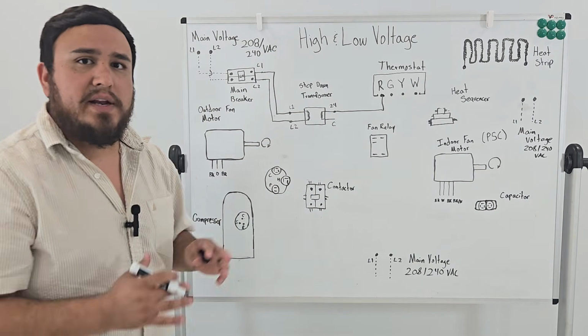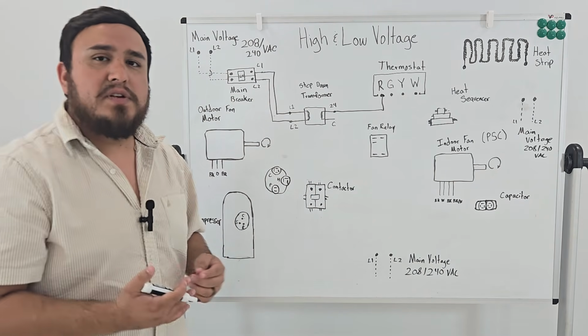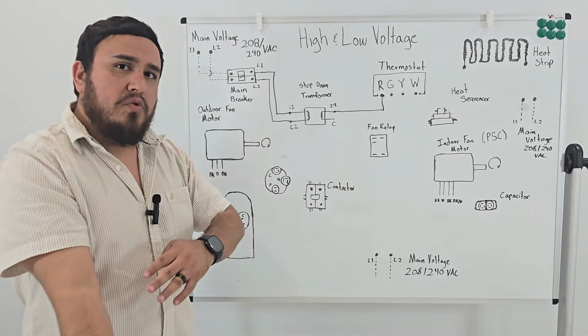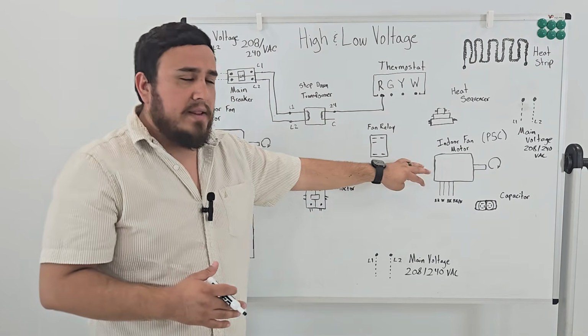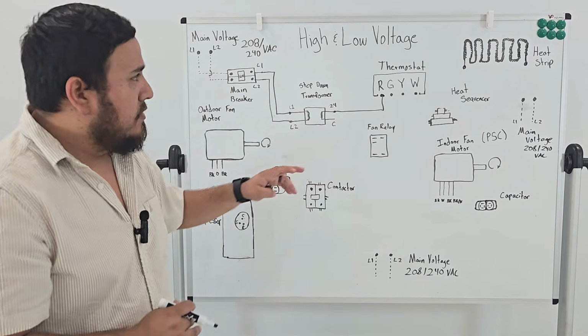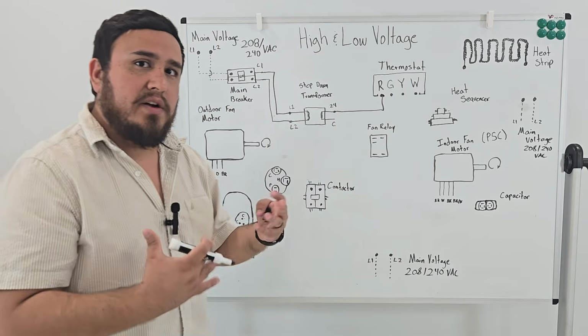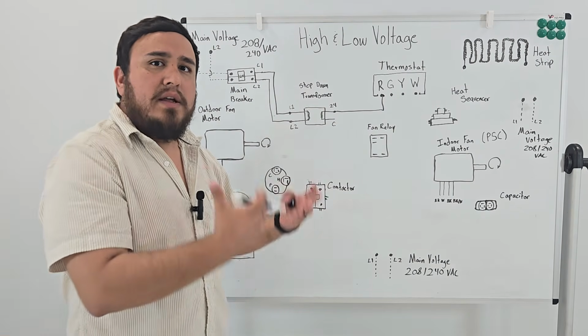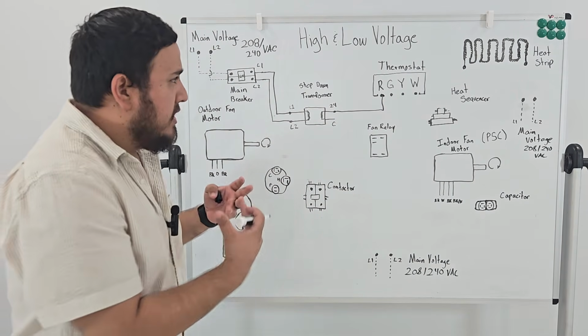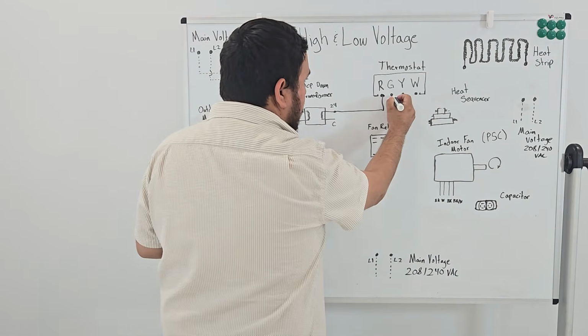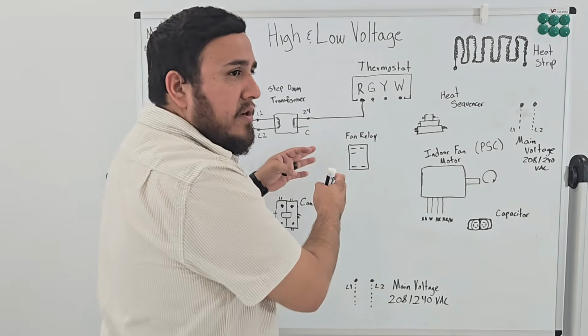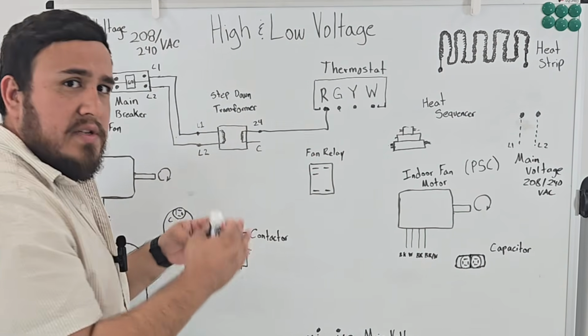The thermostat waits for a signal, either for heating or cooling. We have an indoor fan relay and the indoor fan motor. Green, labeled G, relates to the indoor fan system, so the indoor fan motor and its relay will receive that voltage. Let's connect that.